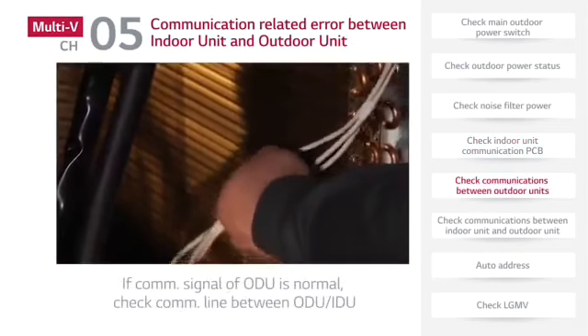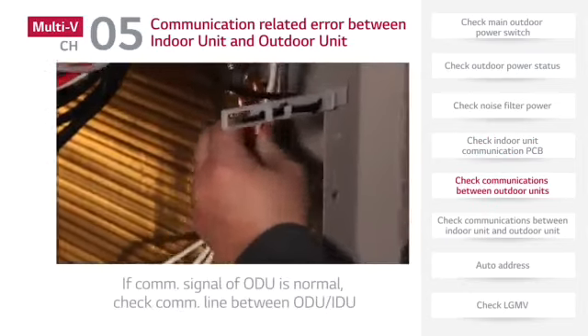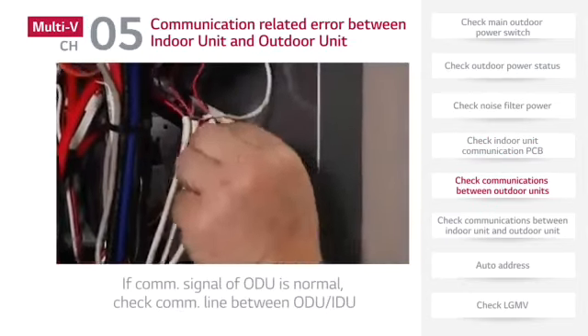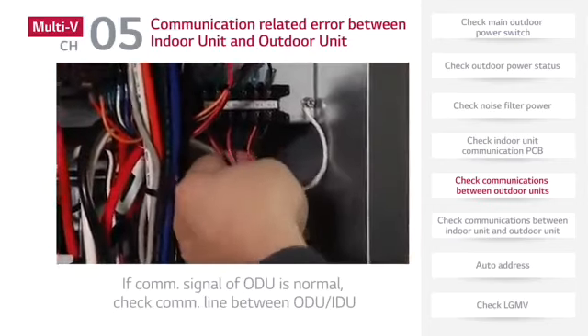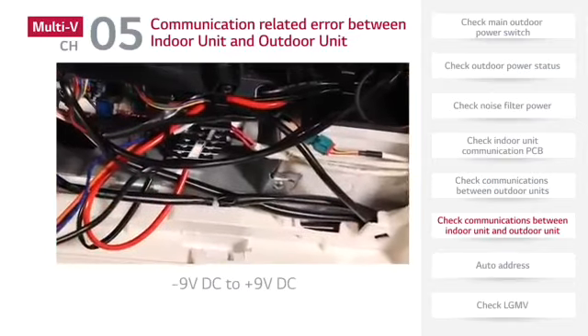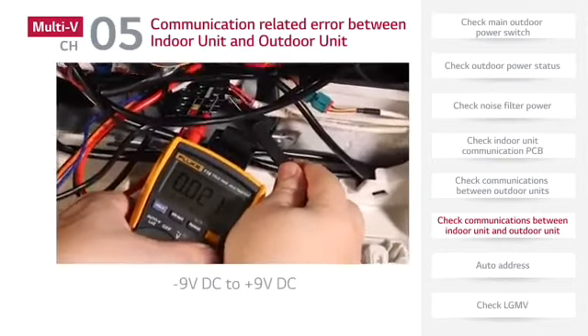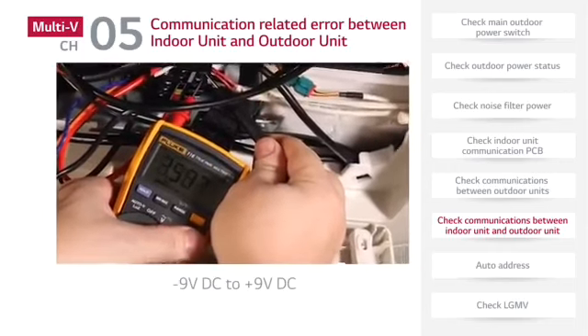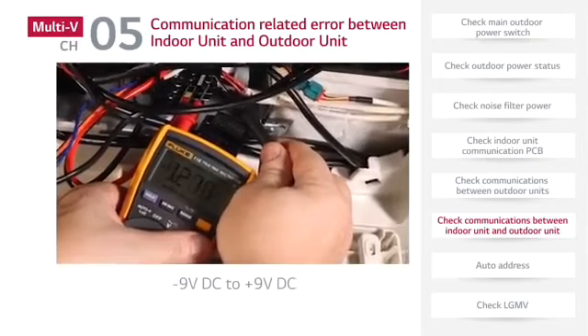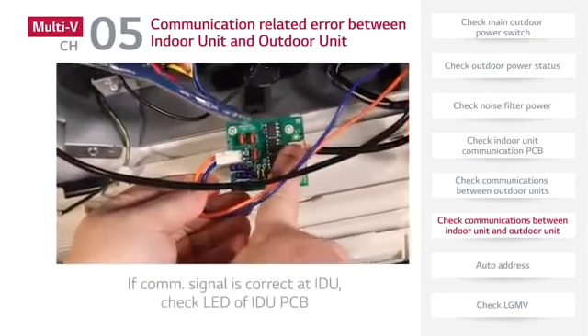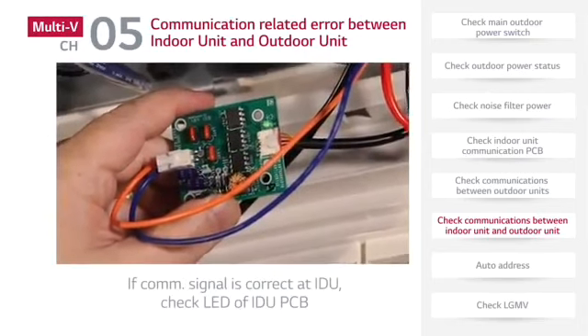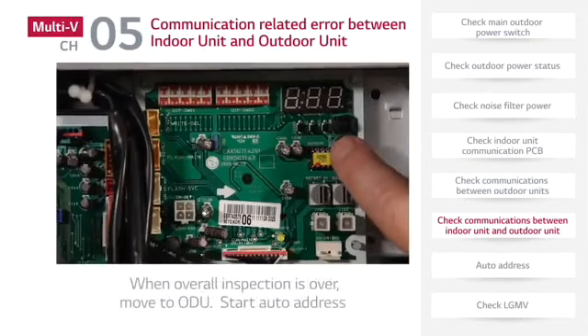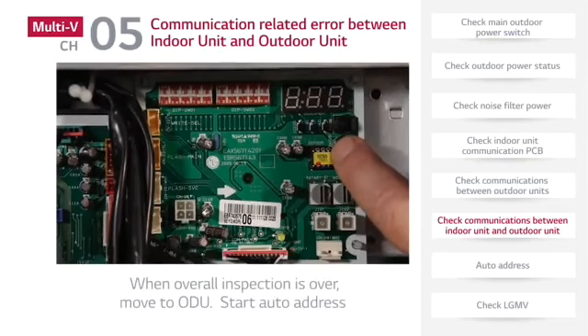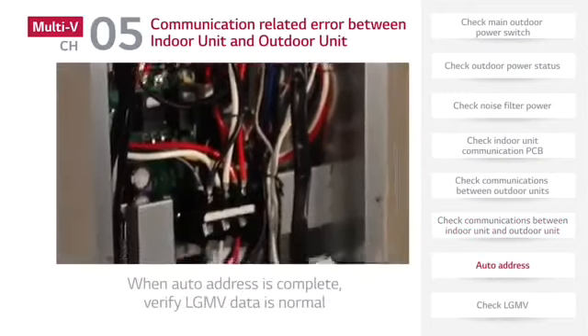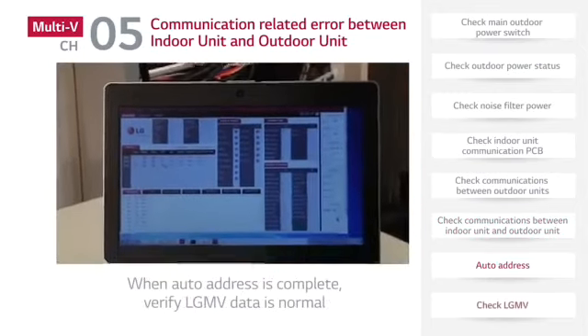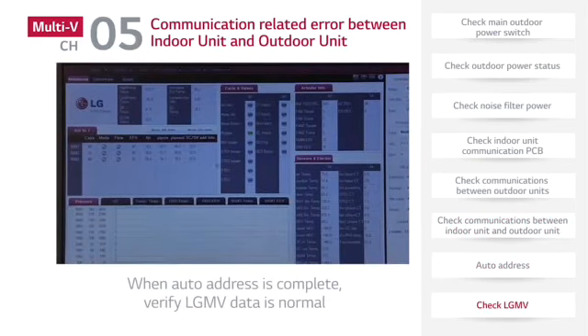If the communication signal of the outdoor unit is normal, check the communication line between the outdoor unit and the indoor unit. If the communication line between outdoor unit and indoor unit is normal, check the indoor unit communication PCB. During standard operation, it is normal for the communication PCB voltage to vary from minus 9 volts DC to plus 9 volts DC. If the communication signal is correct at the indoor unit, check the LED of the indoor unit communication PCB. When the overall inspection is over, move to the outdoor unit to start auto address work. When auto address work is completed, verify LG-MV data to check normal operation.